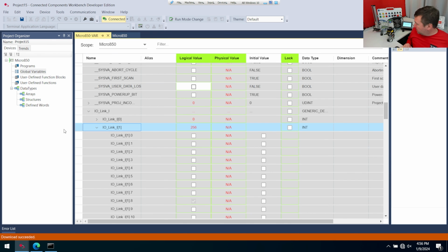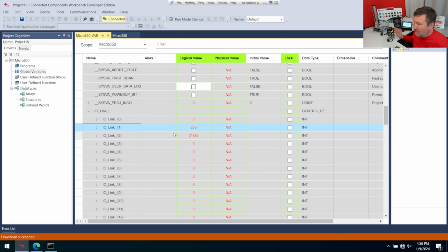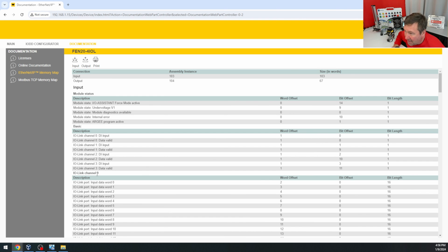So I'm going to stick my screwdriver in, because remember, port one is an inductive proximity sensor and it requires metal in front of it. And we see bit one. And port two is a capacitive proximity sensor, so my hand will work over it. I stick my hand in front of it and we get port two. Now we already saw data coming across on word two as I was moving my finger back and forth. It does say that channel zero's data begins on word two.